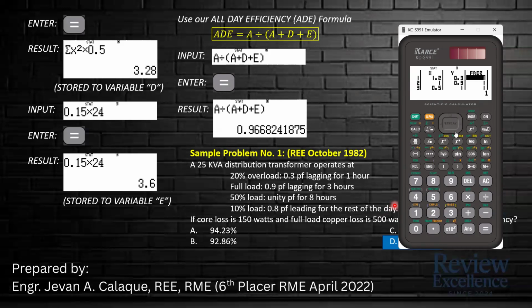And then for the frequency column we input the time. So we have 1 hour, 3 hours, 8 hours, and the remaining hours of the day is 24 minus 1 minus 3 minus 8, so that is 12 hours. And then enter AC, then shift 1, 3, 5, summation of XY multiplied by the rating of the transformer, so that is 25. Then the result here is stored in variable A. The next is the summation of x squared, that is shift 1, 3, 1, then multiplied by the full load copper loss, that is 0.5, stored in variable D. And then next is the core loss, that is 0.15 times the number of hours in 1 day, so that is 24. The result here is stored in variable E.